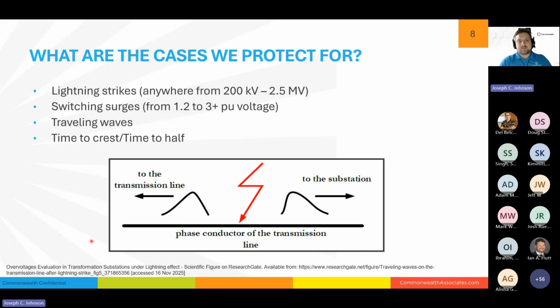And we're going to go over these, and there's two important values in how we test these. There's the time to crest and the time to half. So you'll see a number slash another number and then a time step, which is usually microseconds. And that's what that means. The first number is the time from the very beginning of the wave until it hits its peak. And the second number is till it gets back to half of the value, back down to the before-the-wave value.